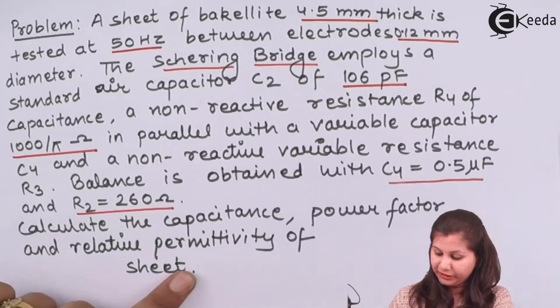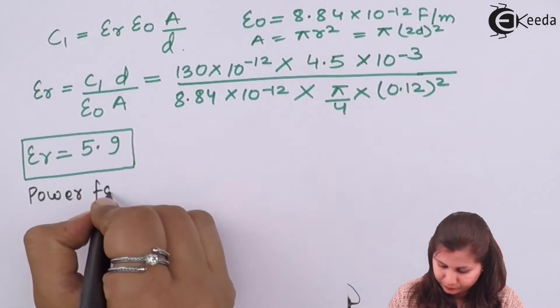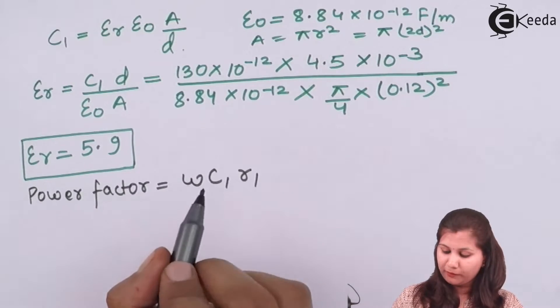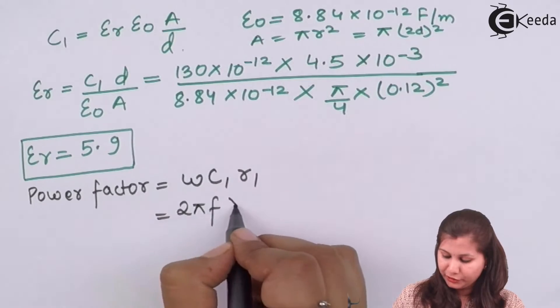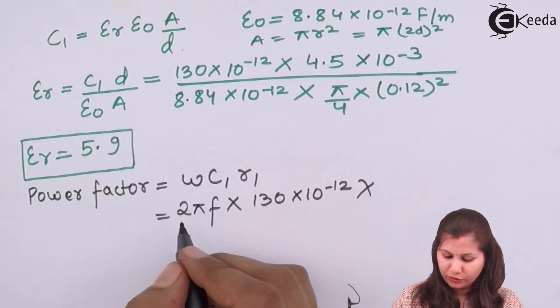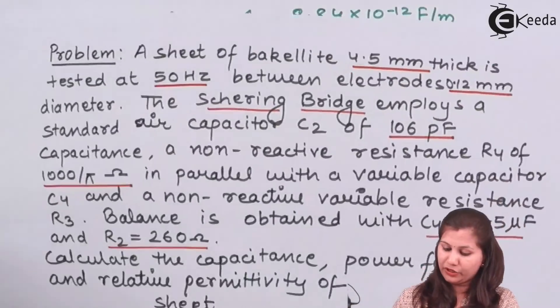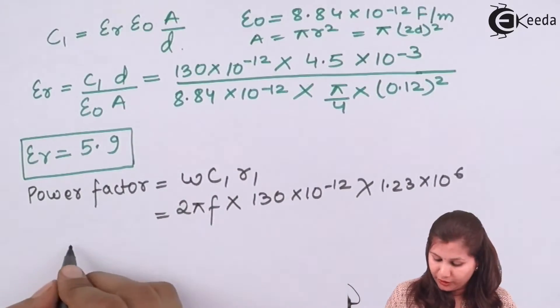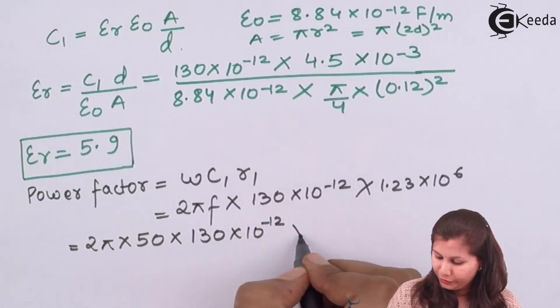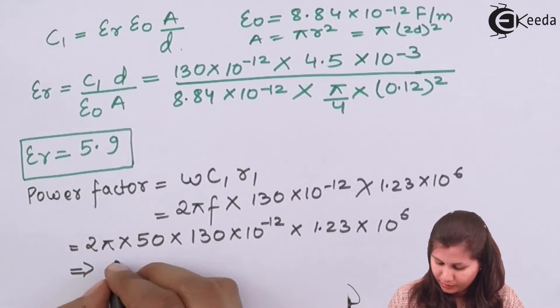We also need to calculate the power factor, also called the dissipation factor. Its formula is: power factor = ωC1·R1 = 2πf·C1·R1. Substituting f = 50 Hz, C1 = 130 × 10⁻¹² F, and R1 = 1.23 × 10⁶ ohms, the power factor comes out to be 0.05.